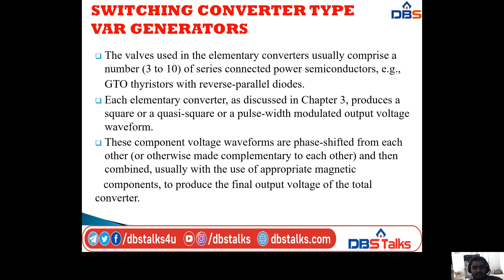For example, I will show a diagram of a typical 48 pulse output voltage waveform generated by the combined output of either eight 2-level 6-pulse converters or four 3-level 12-pulse converters. That is, 8 times 6 equals 48, and 12 times 4 equals 48.